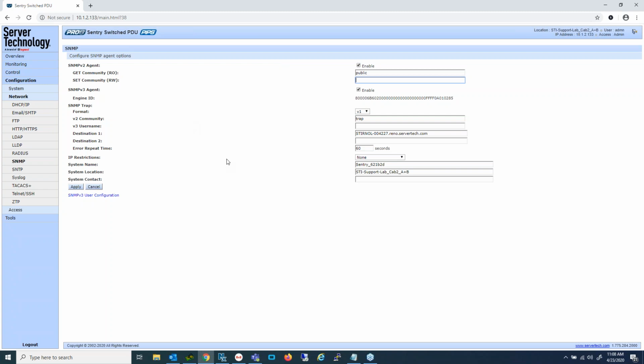Now with SNMP, the notifications, similar to syslog, go out immediately as they occur. There is, however, a repeat time that defaults to 60 seconds. That means if there is an event being reported by an SNMP trap, it will repeat every minute by default until that issue is resolved.